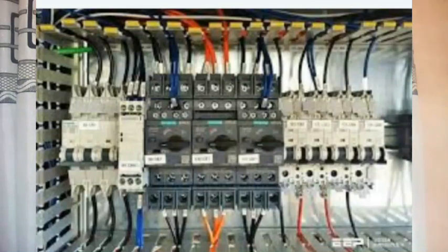So if the design of the remote control circuit in the station has contactors that use 50 volt, then definitely the 50-volt battery bank will equally be used for communication and also for supplying the remote control contactors that need 50 volts for their operation. I believe that the explanation is understood. So the 50-volt battery bank is used for communication, and sometimes it's used to supply the remote control contactors too.